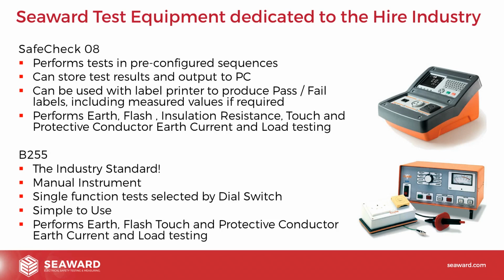It has memory, so it can store results. You can output them to a PC, so you can have a digital record of any of the tests that you've performed. It can also work with label printers, so you can instantly print out a label that can go on the device as soon as it's finished testing. So if anyone was to query it, it's got a label on with a date of test. You can even print out the measured values on that if required. So if you wanted to assign a mini certificate onto your product after it's been tested, you can do that with the SafeCheck 8 solution.